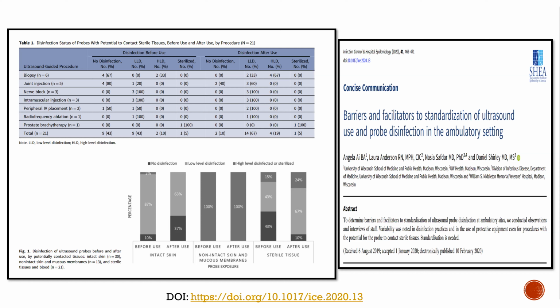And after use, most probes went under low-level disinfection. And so thinking about the types of procedures in the previous slide, how close they were to those insertion sites for biopsies, for nerve blocks, for some of our other different types of procedures where they're using needles, I think that this is important information.